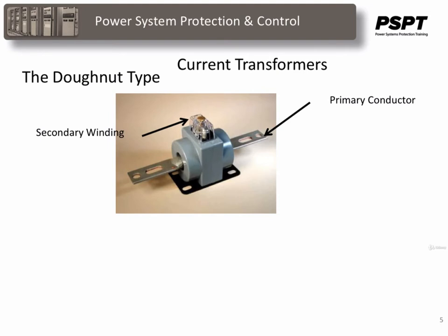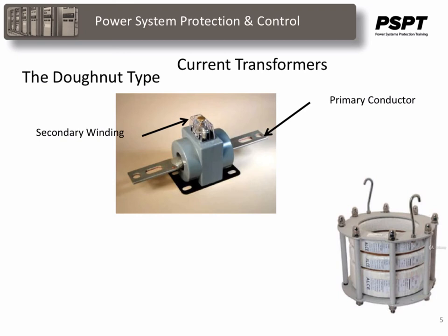If the toroid is wound with 240 secondary turns, then the ratio of the CT is 240 to 1, or 1200 to 5 amp. The 5 amp designates the continuous rating of the secondary winding and is normally 5 amps in North America and 1 amp or 0.5 amp in many other parts of the world. This type of donut CT is most commonly used in circuit breakers and transformers. The CT fits into the bushing turret, and the bushing fits through the center of the donut CTs. Up to 4 CTs of this type can be installed around each bushing.